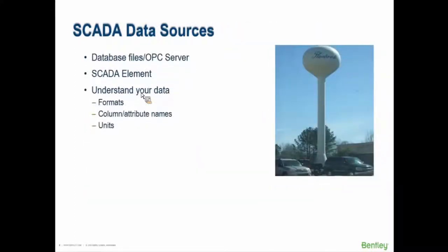A SCADA element is a modeling element that can get data from a couple of sources: some type of database file, or directly from the OPC server. For those who don't work with SCADA very much, OPC is kind of the language of SCADA systems. Somewhere in the heart of your SCADA system is a server running OPC — it gets the raw signals in from the field and puts them in a format where they can be stored or displayed on the human machine interface. We can read directly out of that server if you have data there, but you need to understand how the data is stored, the format, rows and columns, names and units.